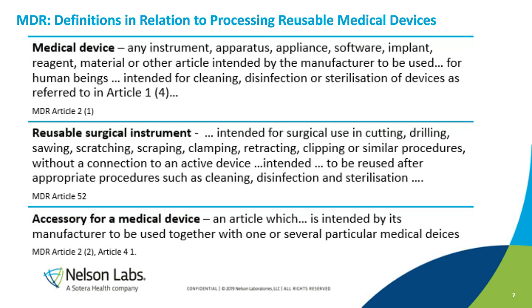But now we want to specify that an accessory for a medical device is intended by the manufacturer to be used together with one or several particular medical devices. And this is also intended to be called a device at this point, all accessories. The definition for manufacturer is a natural or legal person who manufactures or refurbishes a device or has a device designed, manufactured, or fully refurbished.